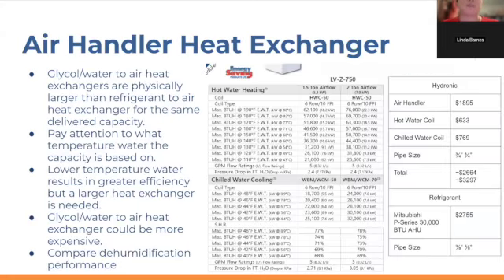Now, so then that kind of covers the water side. On the air handler side, same thing. Water and glycol generally doesn't squeeze into small pipes as nicely as refrigerant does. And so if you have a system that uses water or water glycol mix to deliver the heat into the air handler, you will need larger pipes. For example, for the same size system, same heating and cooling capacity, you would need an air handler with 3/4 inch inlet and outlet, versus in this case, on the refrigerant side, the direct equivalent capacity would only need a 3/8 inch and a 5/8 inch pipe in order to deliver that same amount of heating and cooling capacity.